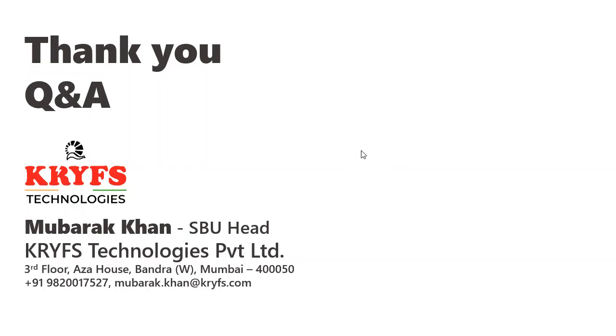How will you connect lug temperature? We have a specially designed lug temperature monitor which can be used. If we can have an offline discussion, I can show you the sensor and we can have a demonstration about that. So we will connect the sensor on the lug directly. The sensor which we have designed is specially tested up to 1 kV, so it can easily be used on the LV terminations. And then we can do the lug monitoring.